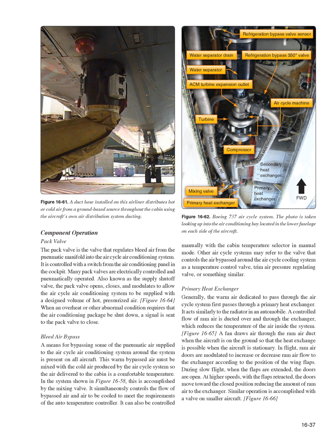It simultaneously controls the flow of bypassed air and air to be cooled to meet the requirements of the auto temperature controller. It can also be controlled on each side of the aircraft manually with the cabin temperature selector in manual mode. Other air cycle systems may refer to the valve that controls the air bypassed around the air cycle cooling system as a temperature control valve, trim air pressure regulating valve, or something similar.